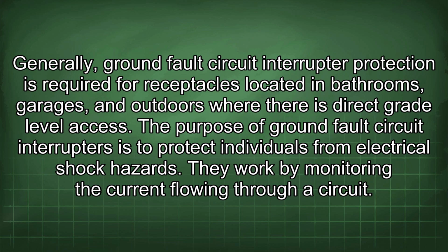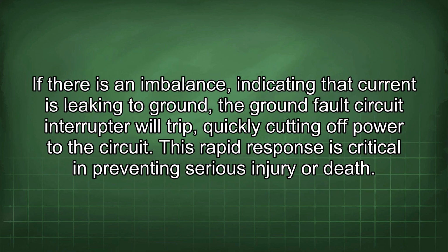They work by monitoring the current flowing through a circuit. If there is an imbalance, indicating that current is leaking to ground, the ground fault circuit interrupter will trip, quickly cutting off power to the circuit. This rapid response is critical in preventing serious injury or death.